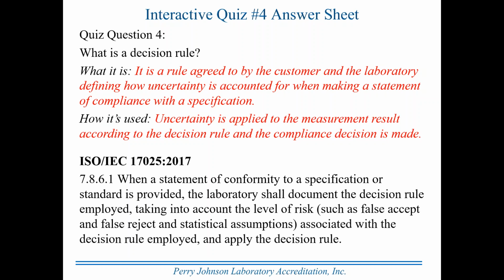Here's where this is found, 7.8.6.1. When a statement of conformity to a specification or standard is provided, the laboratory shall document the decision rule employed, taking into account the level of risk, such as false accept and false reject, and statistical assumptions associated with the decision rule employed, and apply the decision rule. So this is where the correct answer is found, verbatim from the standard. Just keep in mind the decision rule is the instructions telling you how to make the decision about compliance, applying the uncertainty to the measurement result.